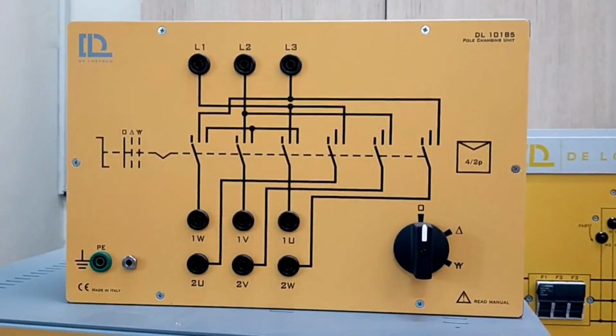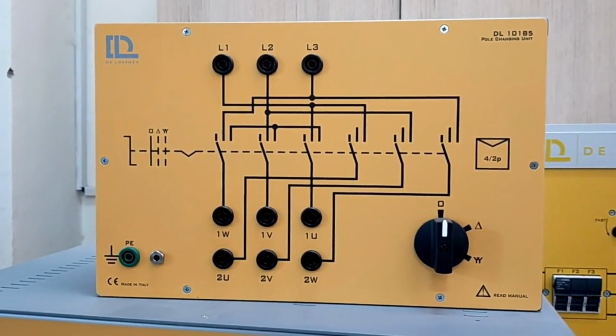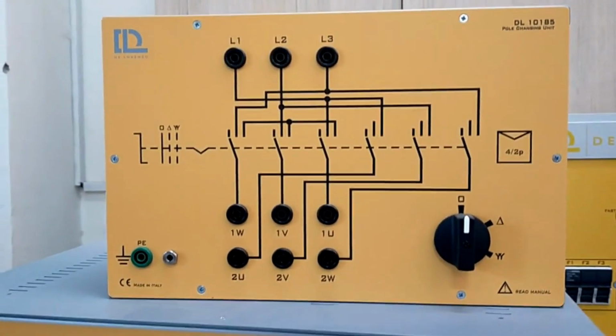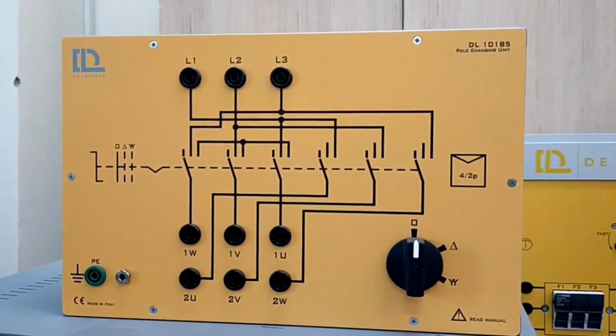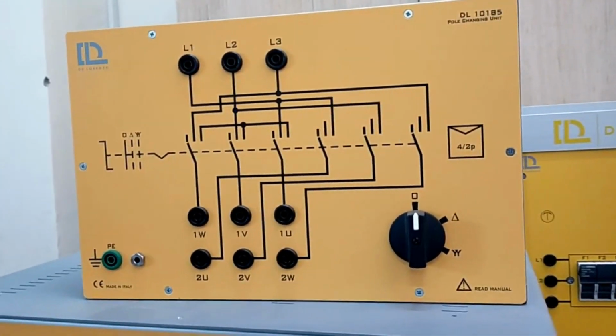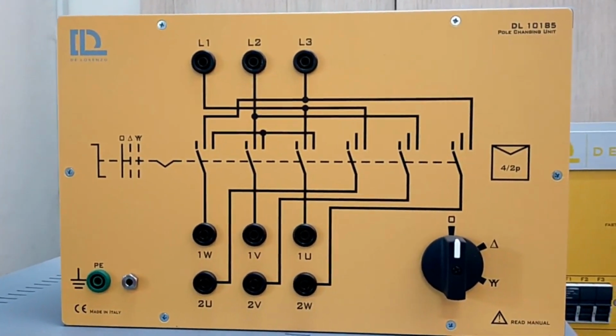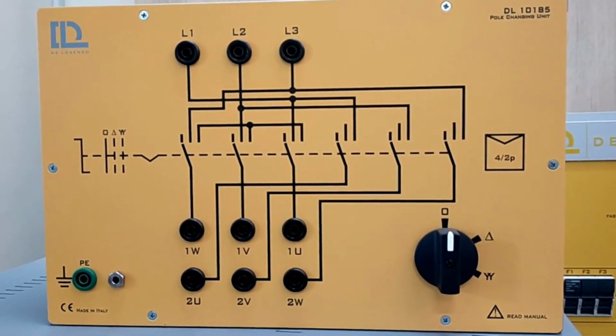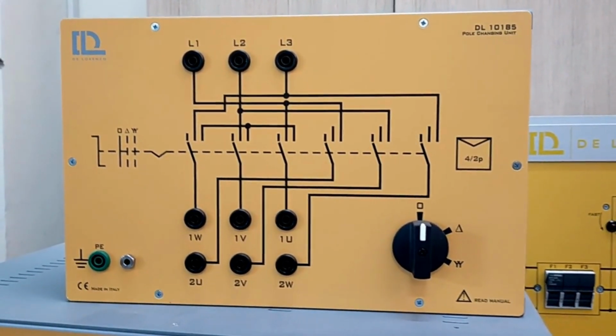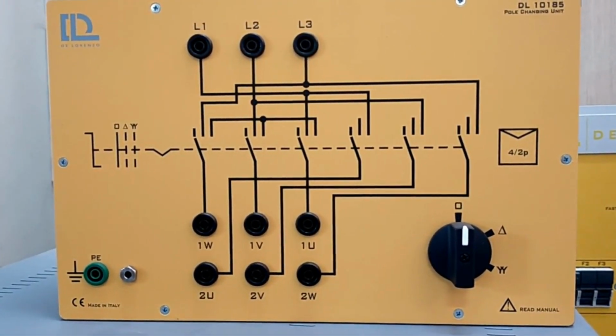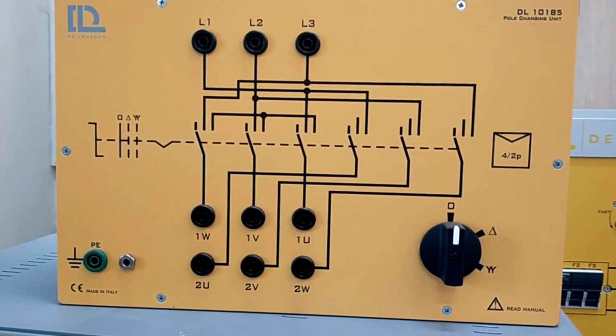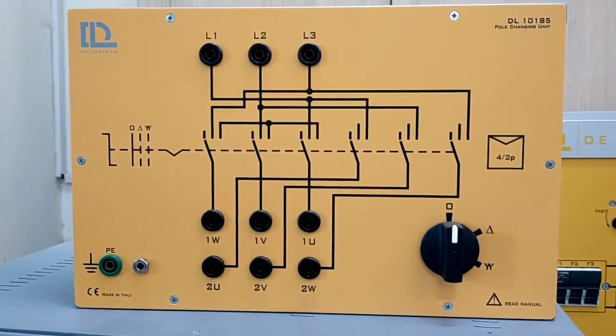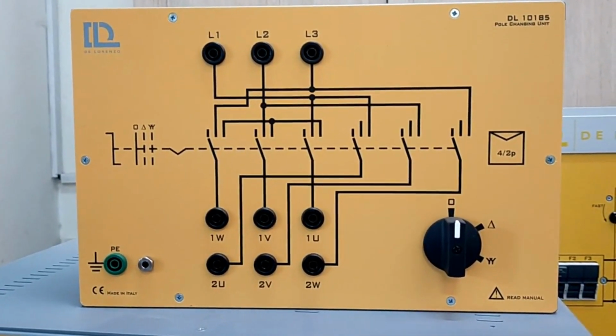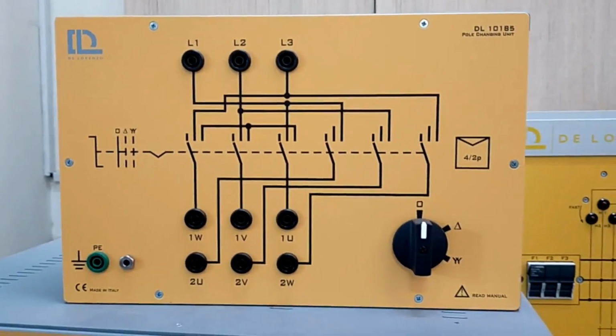Beyond that, this is a pole changing unit, used to make a Dahlander motor, where the poles are changed from 2 to 4. In a Dahlander motor, which runs at 2 speeds, one speed is 2 pole and the other is 4 pole. That Dahlander motor can be made using this pole changing unit.